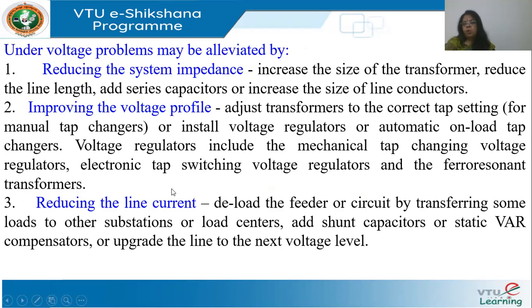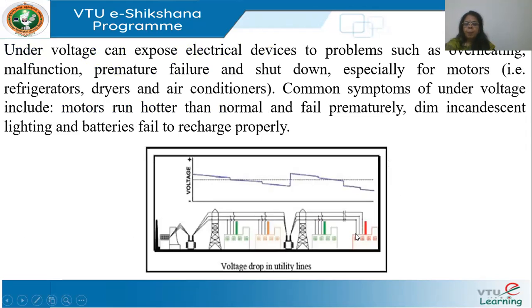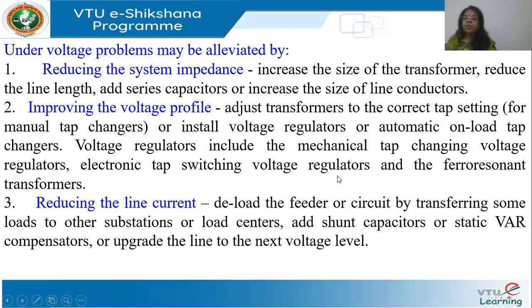To reduce under voltage, which is predominantly caused by drops, reduce the system impedance so the drop is reduced. You can increase the size of the transformer, reduce the line length, add series capacitors, or increase the line conductors — though all these solutions are expensive. Automatic on-load tap changers are another solution: each tap gives around 2% increase, providing limited but useful control.